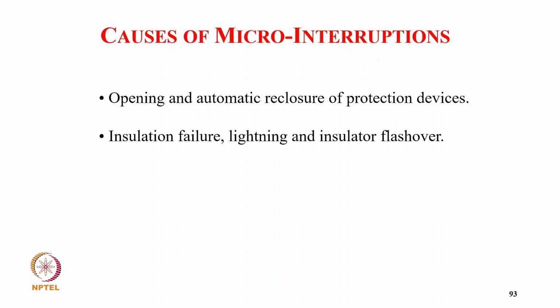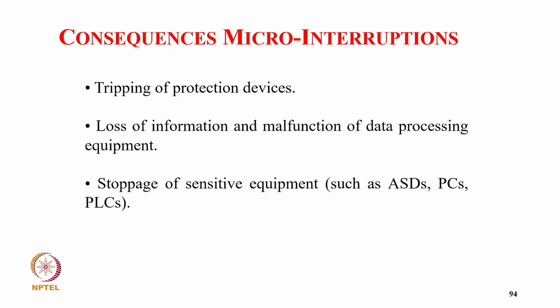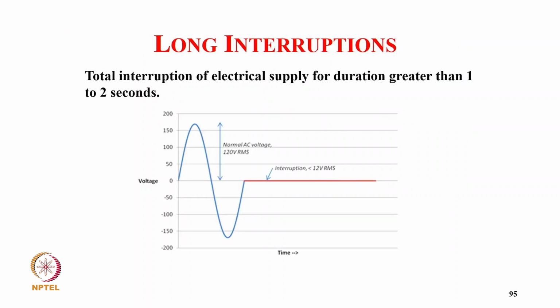The causes of micro interruption are opening or automatic reclosure of protection devices, insulation failure, lightning and insulation flashover. And consequences of interruption: tripping of protective devices, loss of information and malfunction of data processing equipment, stoppage of sensitive equipment such as personal computers and programmable logic controllers.